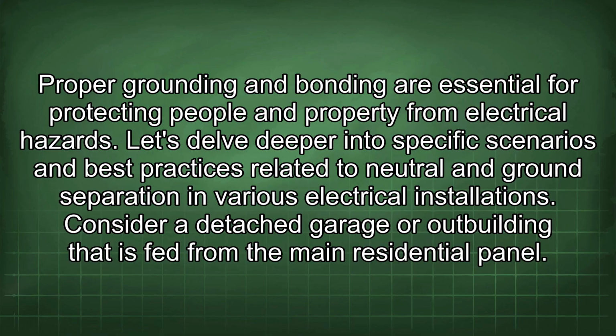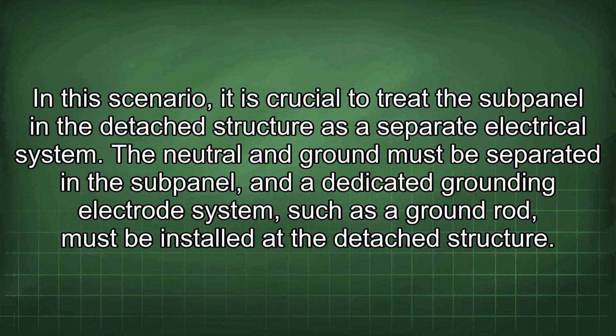Consider a detached garage or outbuilding that is fed from the main residential panel. In this scenario, it is crucial to treat the subpanel in the detached structure as a separate electrical system. The neutral and ground must be separated in the subpanel, and a dedicated grounding electrode system, such as a ground rod, must be installed to the detached structure.